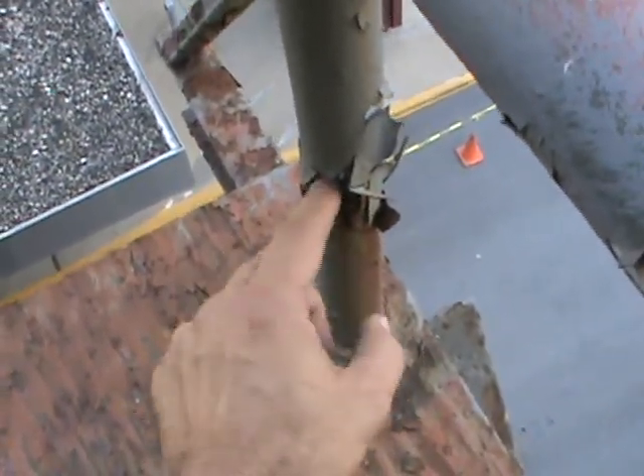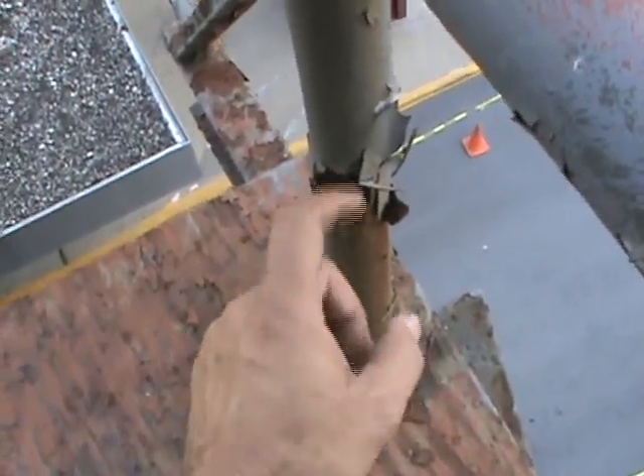But we got a lot of debris inside these, so if I keep putting my finger here, I just keep pulling out rust. So I see just on this case here that water is inside these pipes, and recommendation is 100% of the railings need to be changed out, and we need to have something so that in case you fall, you don't fall through these. Usually these have at least one or two more lines in them, so 100% of all the railings need more lines, either vertical or horizontals, but all these rails should be replaced because it looks like they're rotting from the inside out.